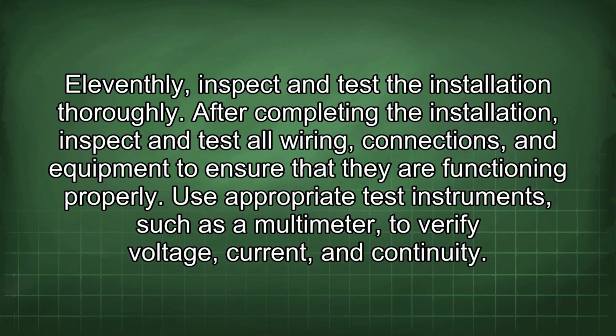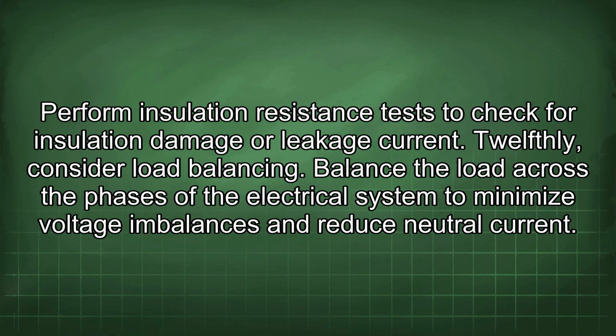Eleventhly, inspect and test the installation thoroughly. After completing the installation, inspect and test all wiring, connections, and equipment to ensure that they are functioning properly. Use appropriate test instruments, such as a multimeter, to verify voltage, current, and continuity. Perform insulation resistance tests to check for insulation damage or leakage current.